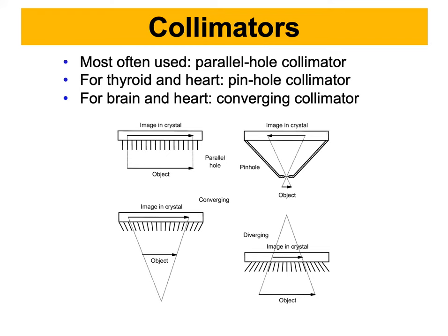We also have the pinhole collimator, shown top right. This collimator is unique because it has a single hole that allows us to magnify or minify the object based on the distance from the object. How far or close this structure is from the object determines whether the image is bigger or smaller. These collimators are used to improve spatial resolution, and one key application is to look at very small objects with high resolution.